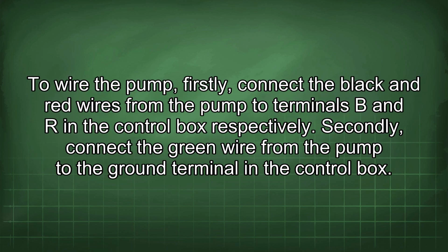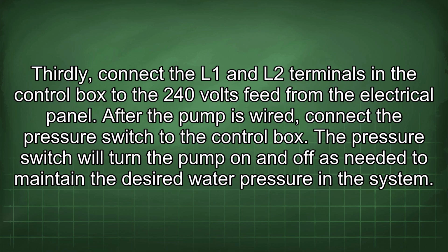To wire the pump, firstly, connect the black and red wires from the pump to terminals B and R in the control box respectively. Secondly, connect the green wire from the pump to the ground terminal in the control box. Thirdly, connect the L1 and L2 terminals in the control box to the 240 volts feed from the electrical panel.